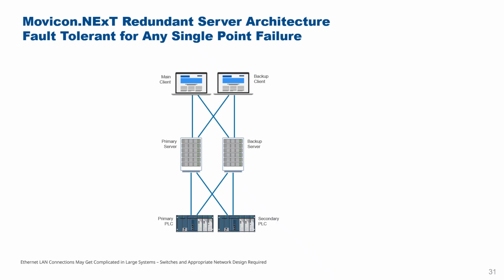You then have a client with a backup client, and then you'd have your primary PLC with its backup PLC. And all of the devices are internetworked in such a way that for every device there is a backup network path as well as the backup device itself. So there's quite a lot of complicated configuration required here around IP addressing, and you may need to use appropriate network redundancy as well. So yeah, your network might be simplified by using STP, spanning tree protocol, or rapid spanning tree protocol. Yeah, that can simplify your network configuration rather than rely on all the networking at the Movicon level.